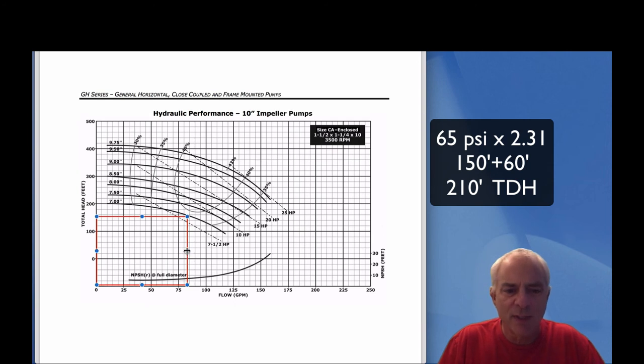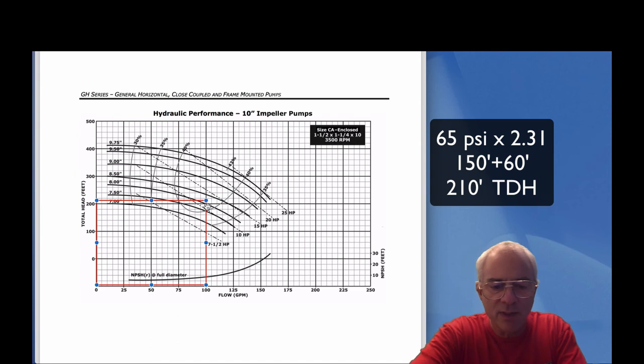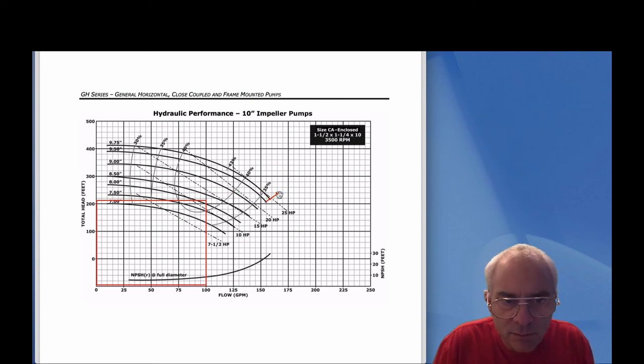We want to be at 100 gallons a minute and our total dynamic head is 210. These increments are about 10 each, so 220 is going to be a little bit less, right around there. We're smack dab in the middle. We're going to put the arrow at our duty point right here.